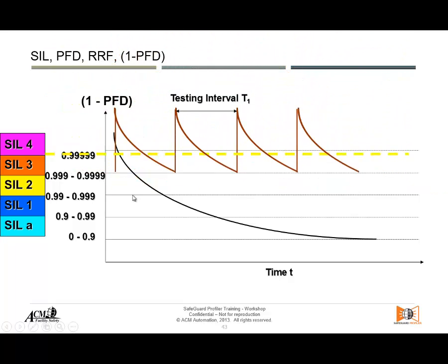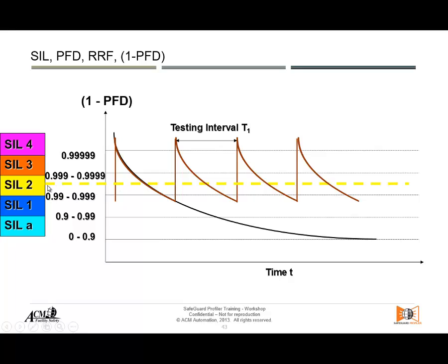If I proof test less often, then my probability of failure on-demand average goes to a SIL 2, for example. So it was a SIL 3, now a SIL 2. Sometimes end users, when you ask them how often they have tested their equipment, say: we've never done a proof test. That means if you thought you had a very highly reliable, low probability of failure on demand equivalent to SIL 3, well, today, if you never tested it, the probability of that equipment failing is very high.